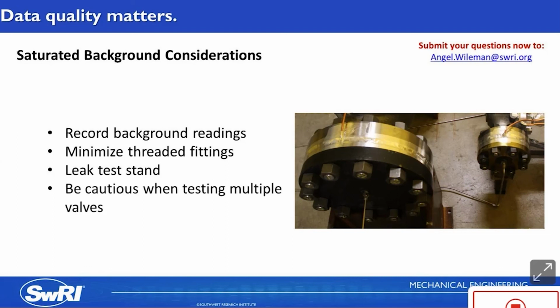And be cautious when testing multiple valves simultaneously. You're going to have an increase in your plumbing components, and that's going to lead to more potential leak sources that can saturate your background. And you also need to be able to apply pressure independently to each valve to know which valve has an elevated leak concentration. Just remember that elevated backgrounds do not always indicate valve leakage. It could be from anywhere on the stand, so it's important to minimize the potential leak paths.